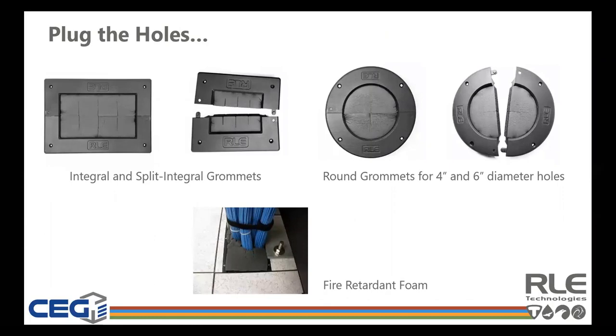So the first best practice is plugging the holes. Tim mentioned this earlier, and I chimed in a little bit when we had the pictures of the holes around the perimeter of the room and under the rack. So one of the easiest and most cost-effective best practices to implement in the data center is to plug all the holes in the data center environment. We all know this, yet many of these solutions are only partially implemented or never maintained over time.